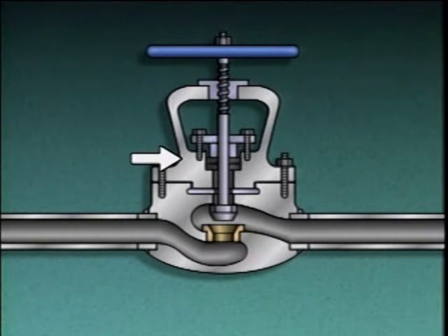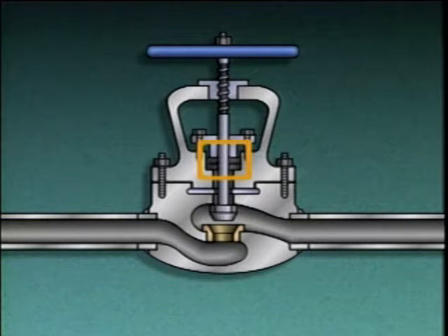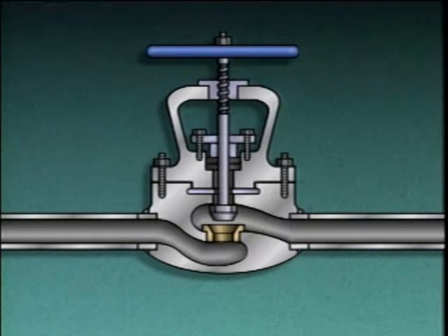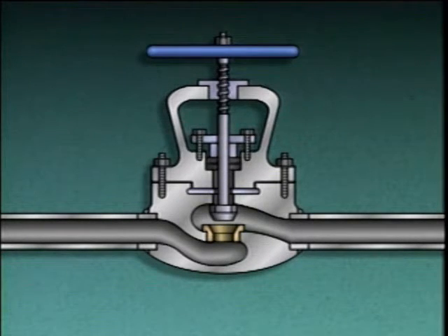The valve bonnet seals the top of the valve body. The stem extends through the bonnet and into a space called a stuffing box. The stuffing box holds the packing, which is installed around the stem. The packing is flexible and leak resistant, and it prevents leakage from the valve along the stem. The pressure applied to the packing by the packing gland is adjusted using gland nuts, so that the valve stem can be moved as the valve is repositioned but leakage does not occur around the stem.